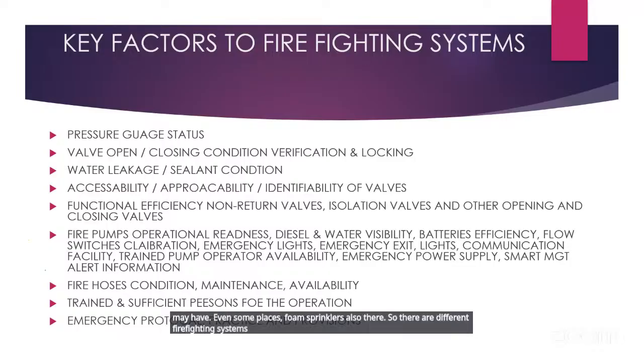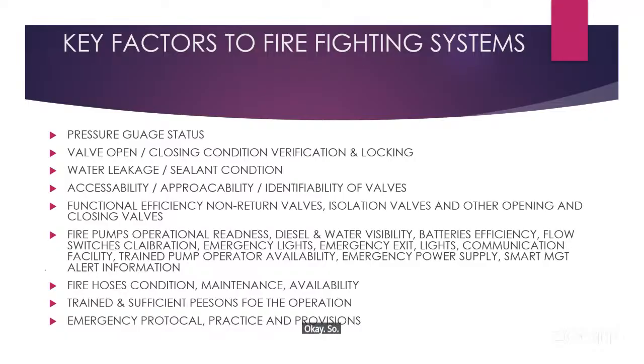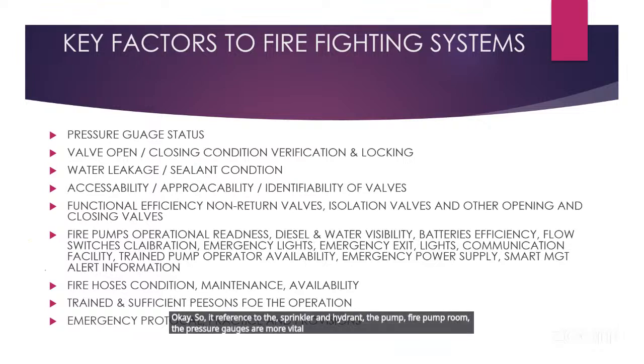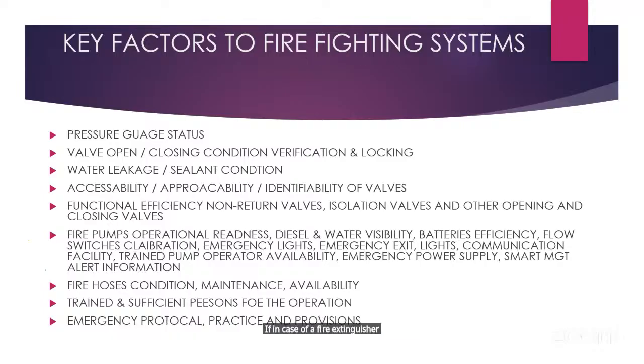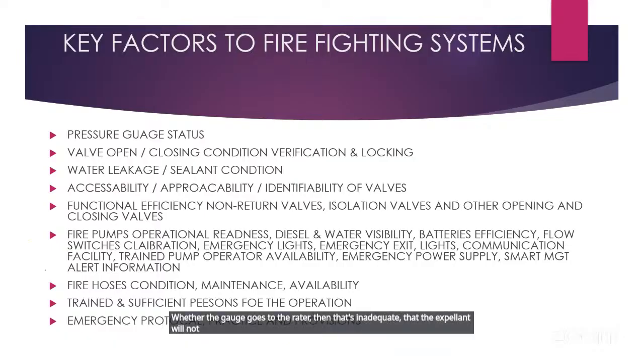There are transformers, we have nitrogen based systems, and there are a lot of firefighting systems. Okay. With reference to the sprinkler and hydrant, and the fire pump room, the pressure gauges are vital instruments. The pressure gauge is the live indicator of the healthiness of your systems. In the case of a fire extinguisher, if the gauge goes to the red, it is inadequate, and the extinguishant will not come out through the push of the expellent.